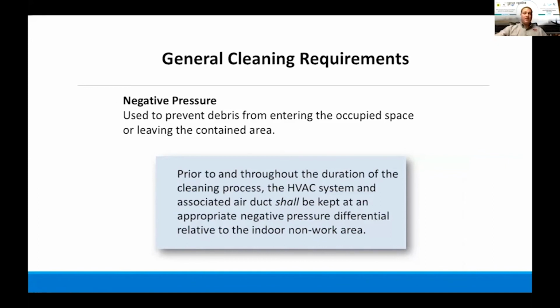If you notice here, the way we go about our cleaning so far, from what you might be able to see, is that it coincides with a lot of the stuff that you already do within indoor air quality and how you clean up an airspace. Now we're just taking a lot of that and putting it into the HVAC system. So negative pressure is used to prevent debris from entering the occupied space or leaving the contaminated area. Prior to and throughout the duration of the cleaning process, the HVAC system and associated air duct shall be kept at an appropriate negative pressure differential relative to the indoor non-work area. Basically saying that we're going to control the environment in which we are cleaning.